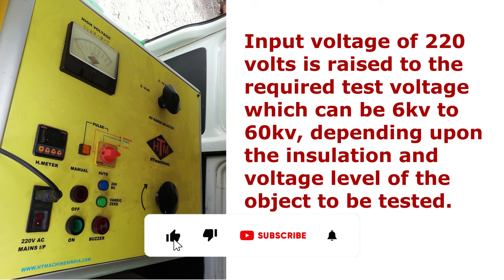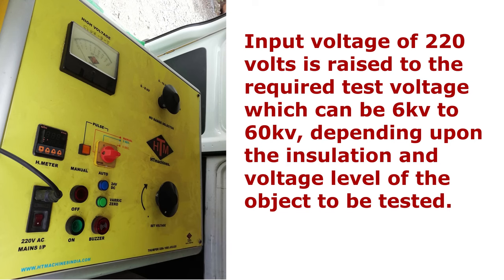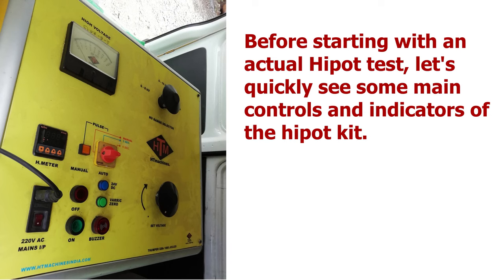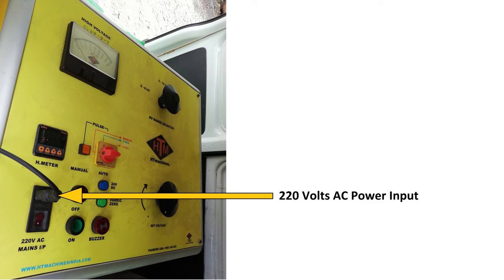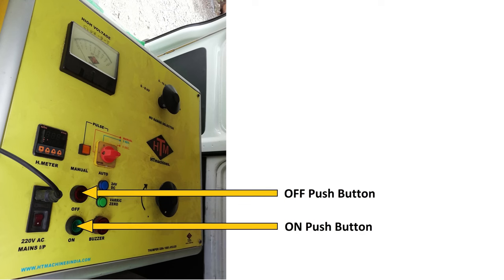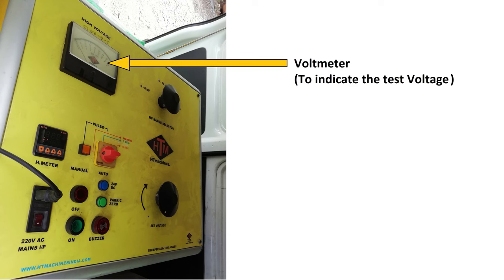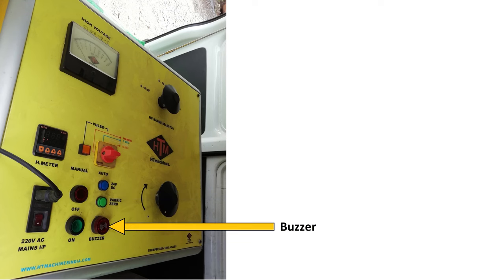This is how the hipot test is carried out. Input voltage of 220 volts is raised to the required test voltage, which can be 6 kV to 60 kV, depending upon the insulation and voltage level of the object to be tested. There are also some other necessary components installed inside the test kit. Let's quickly see some main controls and indicators of the hipot kit. This is the 220 volts AC power input to the kit. These are the on and off push buttons. This is the knob to raise the test voltage gradually, this is a voltage range selector, this is the voltmeter to indicate the test voltage, and this is the leakage current indicator. These are indicators and this is the buzzer.